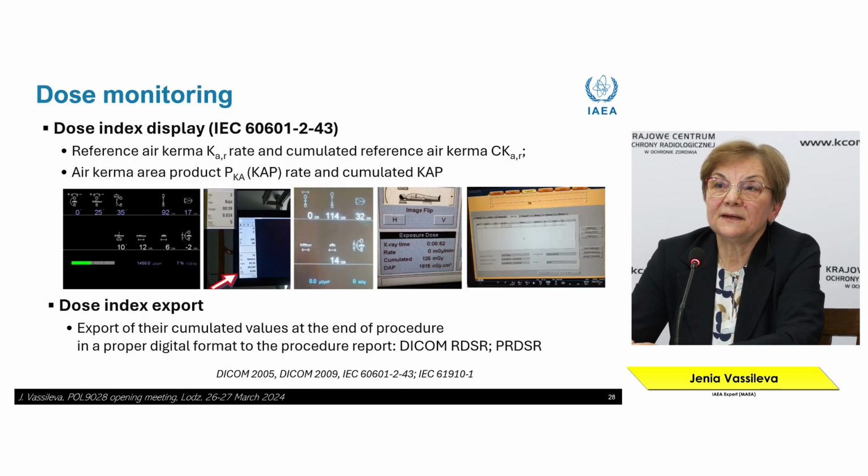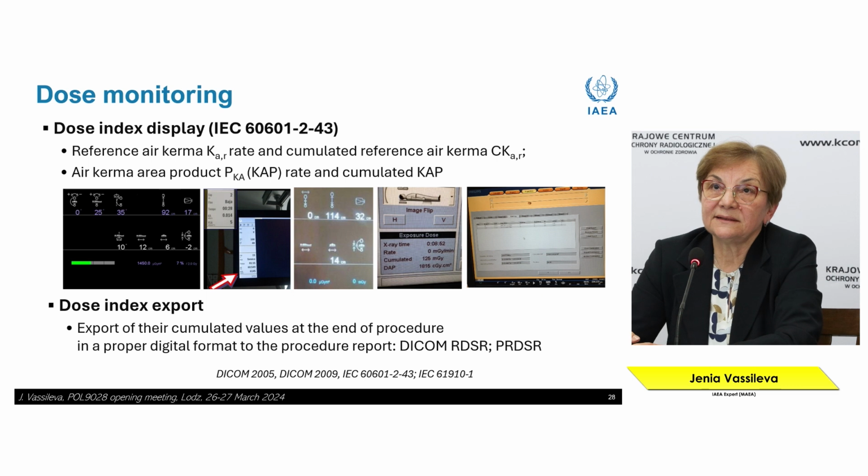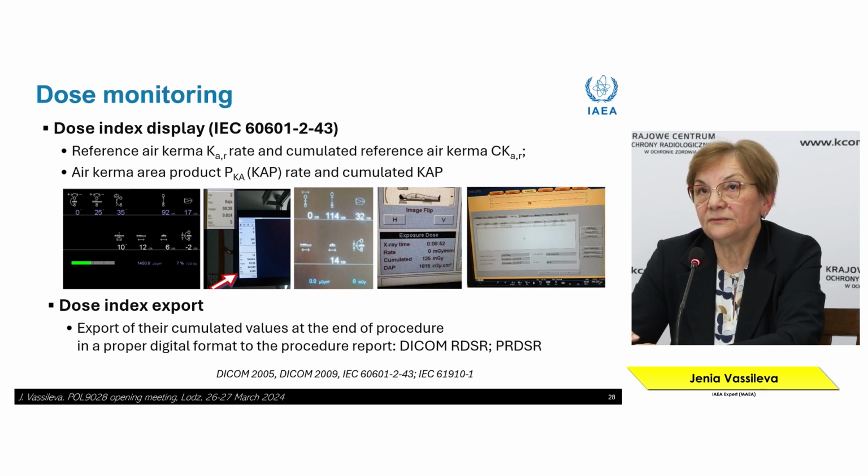So yesterday I discussed the dose displays. There are two different dose quantities that also have to be verified. This I did not mention yesterday, but having displays is not enough. These displays should also be verified, and this is the task of the medical physicist during the commissioning and during the periodic tests.